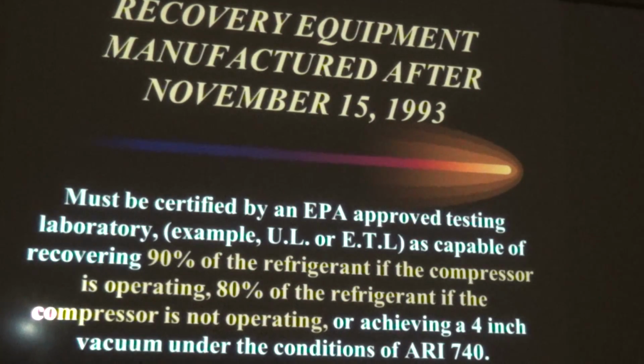If it was made after November 93, two things. One, it has to be certified by an EPA approved testing lab, an example being, like I said, Underwriters Lab. If you look at our yellow-black recovery machines that we have, they have a UL rating saying this is capable of recovering not 80 but 90% of the refrigerant if the compressor works, or 80% of the refrigerant if the compressor does not work, or achieve a 4-inch vacuum under the conditions of ARI 740.